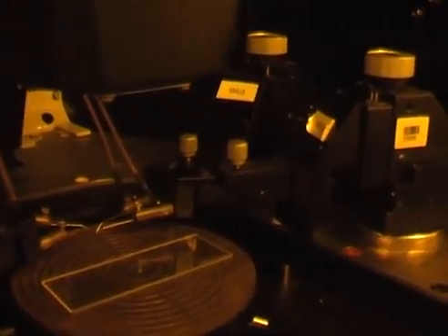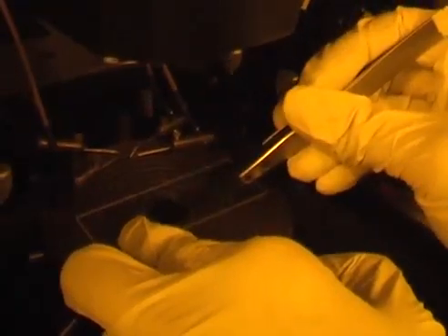Here is the coarse control to make sure that the probes have been lifted up so that they won't scratch your sample during the loading. Then we can load your sample. Put your sample onto the glass slide, and then move the sample in beneath the probes.